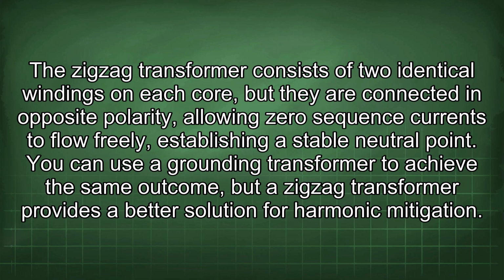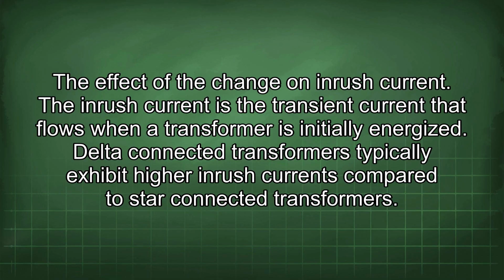The effect of the change on inrush current. The inrush current is the transient current that flows when a transformer is initially energized. Delta-connected transformers typically exhibit higher inrush currents compared to star-connected transformers.